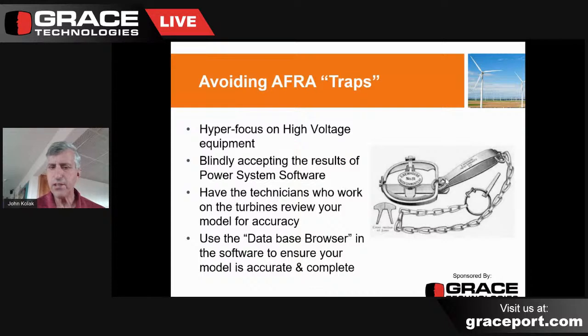I often use a database. Each software usually has a database browser in it, which actually has the settings on every breaker and every footage on cables, whatever. I definitely use the database browser to make sure that the settings you have on your devices are correct, and that every unit in the system is in fact going to operate. In other words, it's connected to the system and it will actually interrupt current flow. Many times, if you forget to enter the data of a piece of equipment, it may allow you to run the calculations, but it obviously wouldn't take into account the clearing time or the response time of the system if you didn't have that model properly. So use the database browser to make sure that all the system has appropriate inputs into them and they will operate using proper calculation methods.